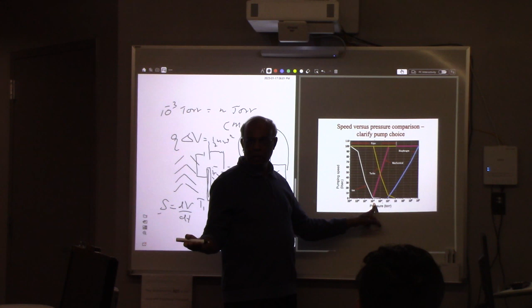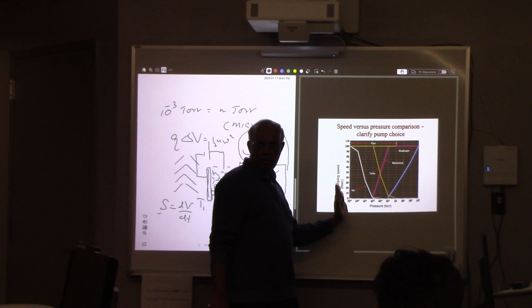Mechanical pumps, even diaphragm pumps, stop working after about 1/10 of a millitorr. That doesn't work at all here. So mechanical pumps or roughing pumps only work at high pressure, they're pretty much dead here. But ion pumps, turbo pumps, diffusion pumps, they all pick up at low pressure. So it's good to have this chart. These are the basic pumps everybody should know.